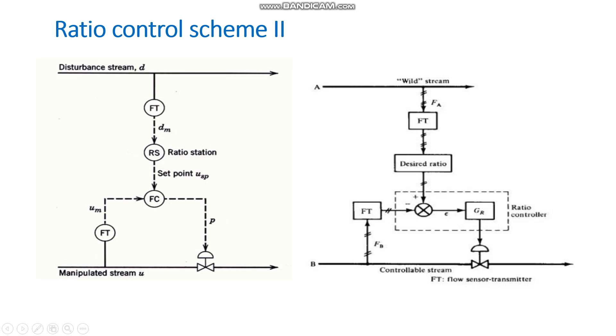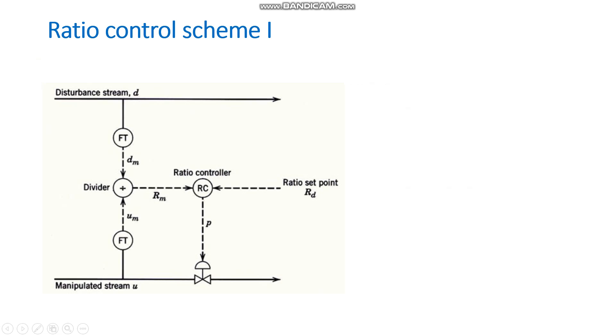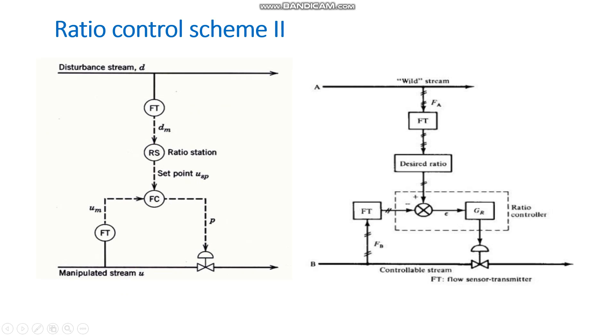In scheme two, the same disturbance variable and manipulated stream are present with a set point. From the ratio station, the set point is given to the flow controller. In scheme one, the set point was given directly to the ratio controller, but in scheme two, the flow meter measures the wild stream flow and the transmitter sends it to the ratio station, which then provides the set point to the flow controller.